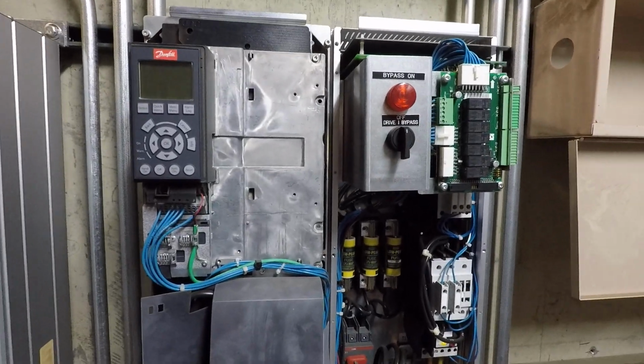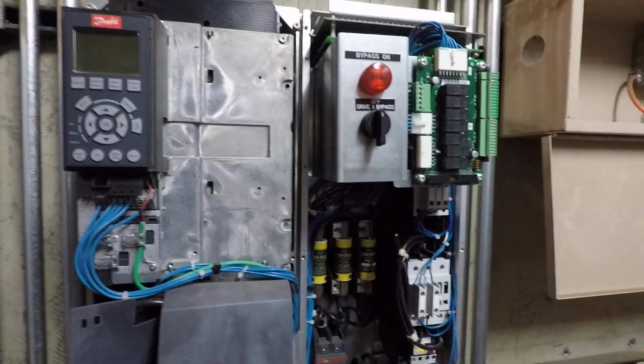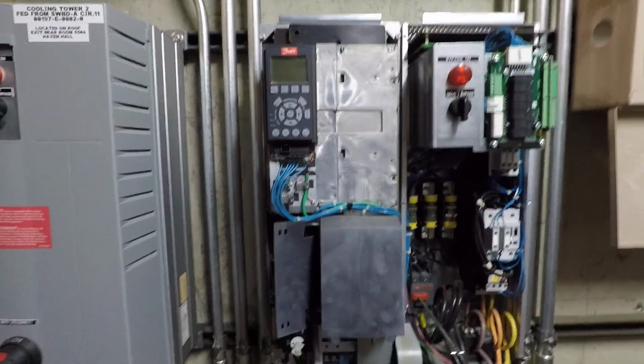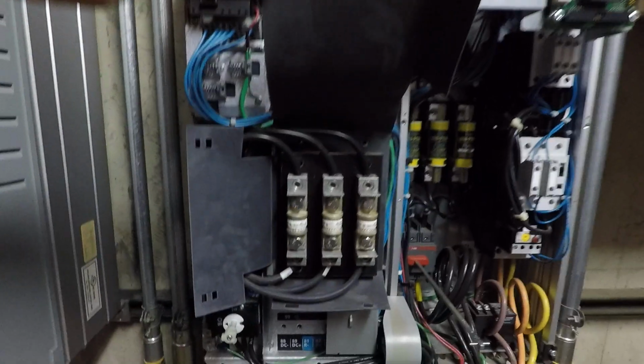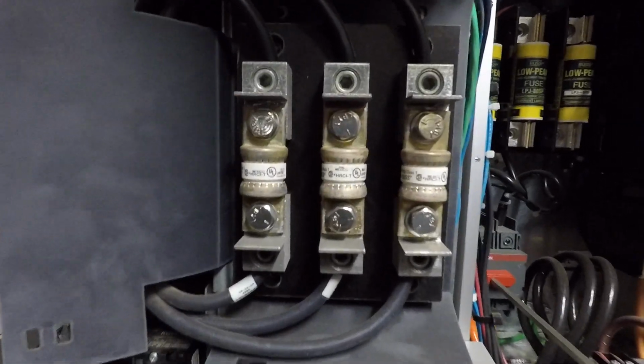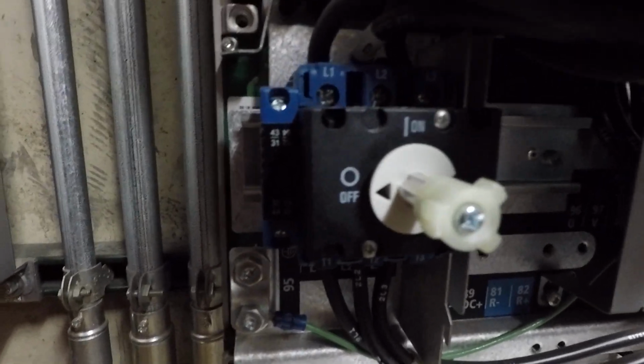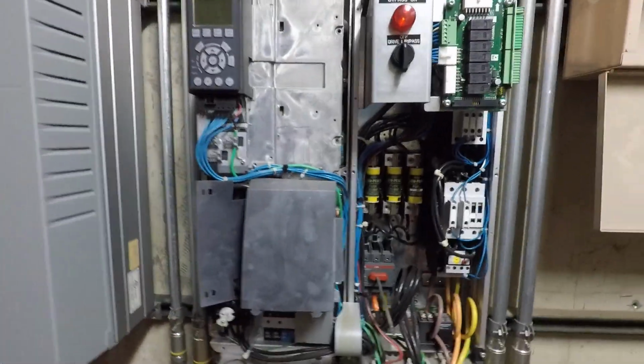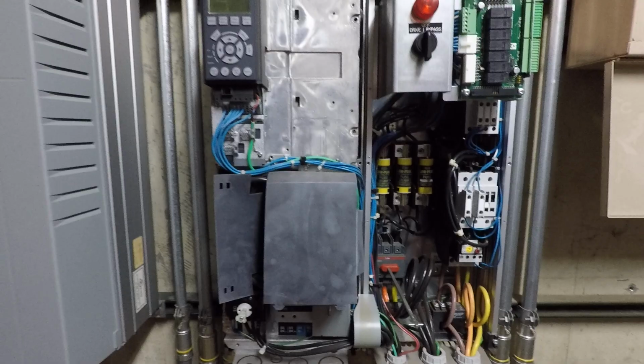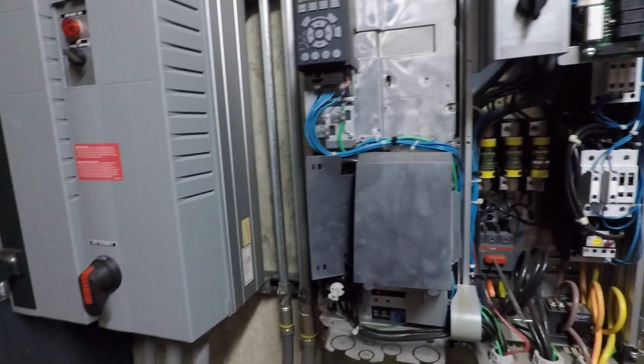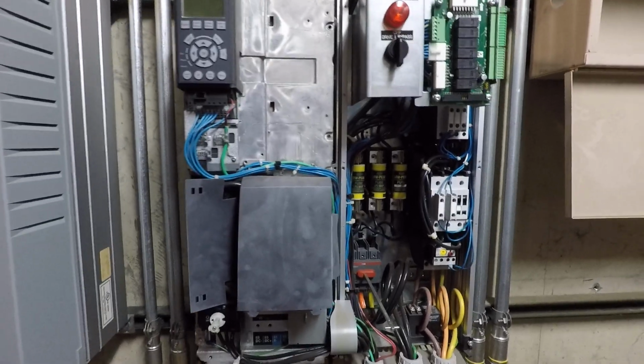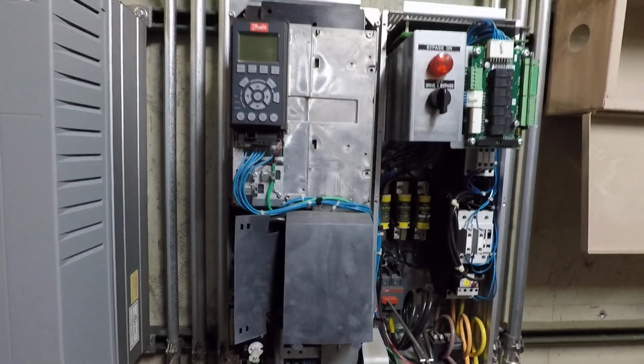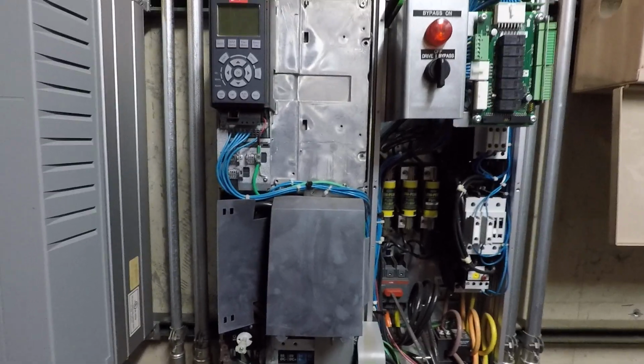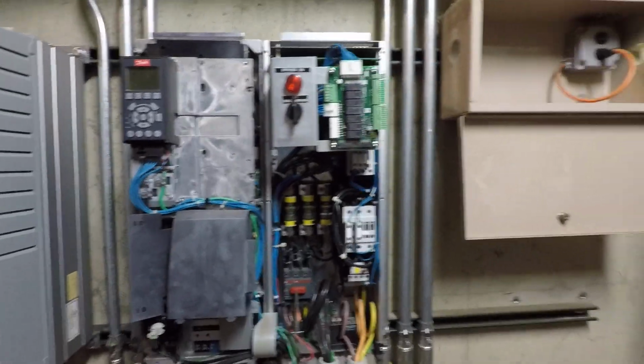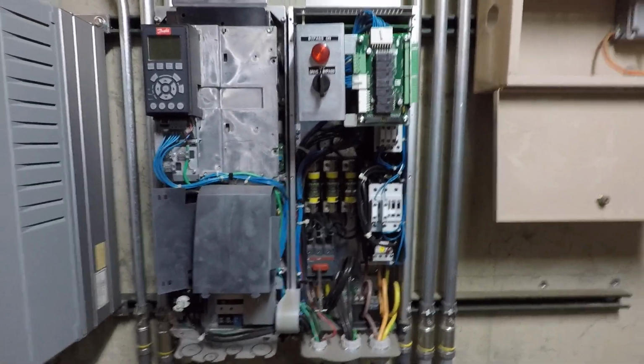I'm taking the cover off, and you will see that the drive on the left here has integrated fuses built right into the drive and an integrated disconnect switch. So what happens when they add those items on, it increases the lead time, so it kind of makes it not really off the shelf anymore. Those are two options that customize the drive, and they're obviously required to have. You can't delete those when you have this whole setup, the whole Danfoss package.